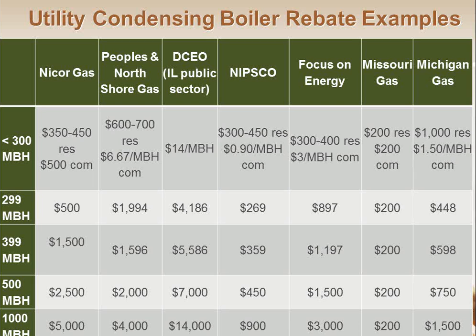If it's a public building in Illinois, like a fire station or school or village hall or something like that, you don't get your rebate from the gas company. You get it from DCEO, Department of Commerce and Economic Opportunity, and the dollar amounts are huge. So if you do any public sector work, you should definitely be looking at these boiler rebates. The dollar amounts are big. A 1 million BTU boiler is a $14,000 rebate. That basically buys them a boiler. You still got to pay to install it and the labor and all that, but you're basically getting a free boiler. But even the private sector ones are pretty good.